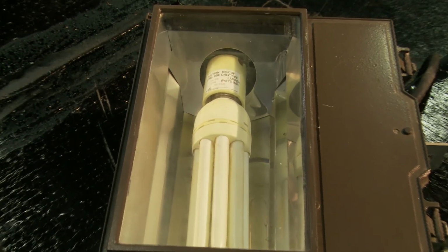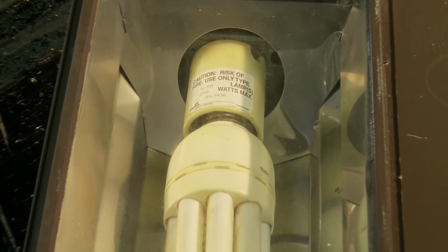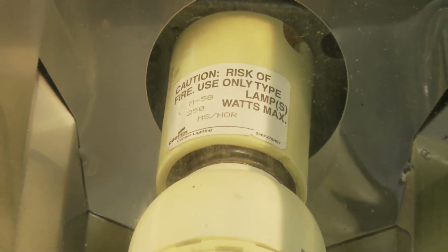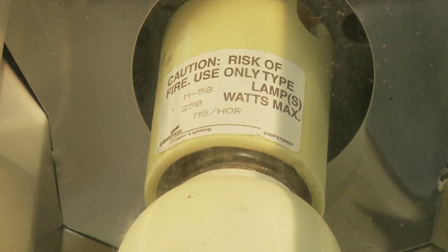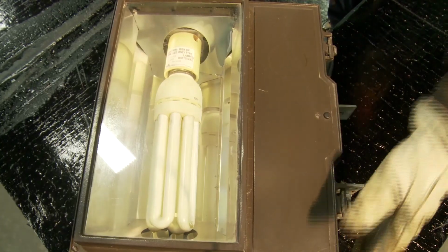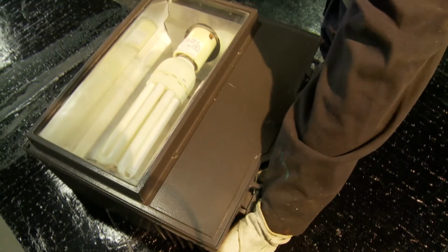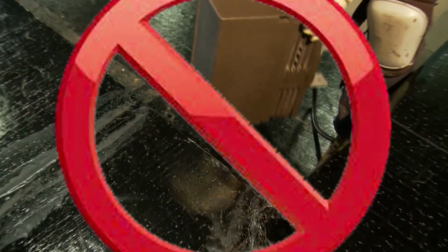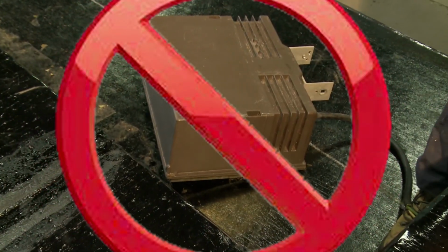Generally, these light fixtures contain high-temperature bulbs, such as halogen bulbs, that if switched on after the crew has left for the day, can produce temperatures high enough to ignite combustible roofing materials left lying around the roof at day's end. A potential fire hazard exists when the light fixtures are not disconnected, removed from their mounting, and laid face down on or near combustible surfaces during roof operations.